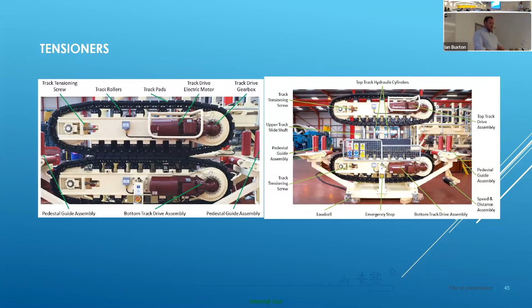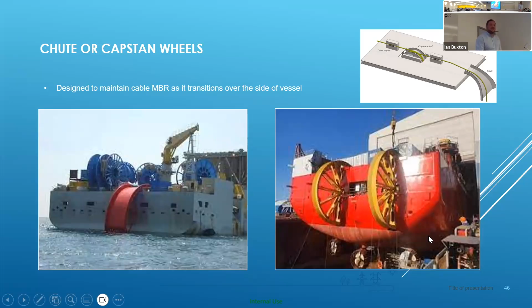Chute and capstan wheels - the chute is probably a 10-meter MBR. A cable has a minimum bending radius for installation, and you do not want to exceed that minimum bending radius, because you can start compromising the components of the cable. Europeans tend to have the chute, which you can see on the left. The Norwegians are big fans of the capstan winch, which really looks after your cable. Nexans, a big cable manufacturer, have capstan wheels on all their vessels, and it's seen to be very nice to the cable - kind of the Rolls Royce of cable installation.